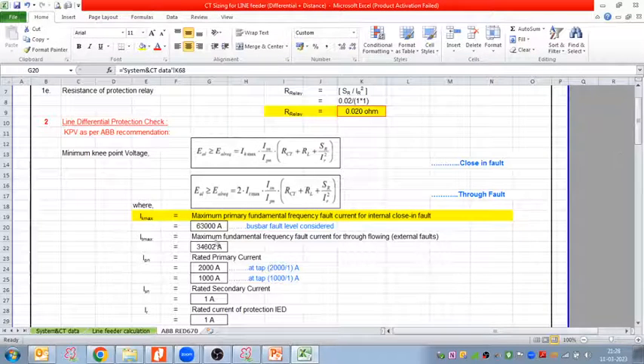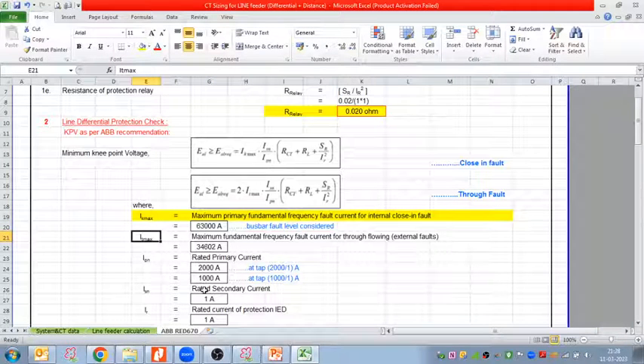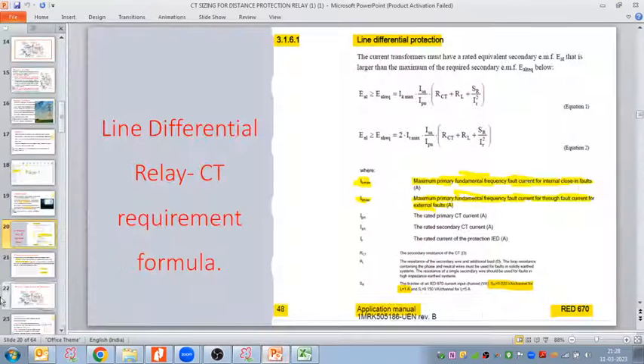So IK max is 63 kiloampere. IT max is the through fault current calculation. Now we will discuss how to calculate it. Yesterday we wanted to calculate the through fault current only. So 63 kiloampere is my substation fault current, which we are considering as the close-in fault current, and IT max is the through fault current, which we have to calculate based on the protected line impedance.